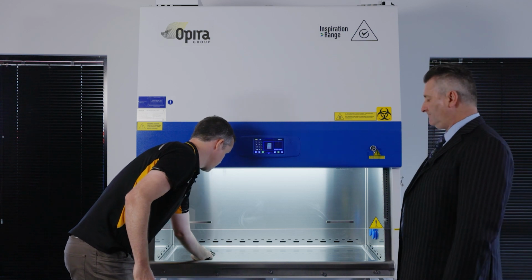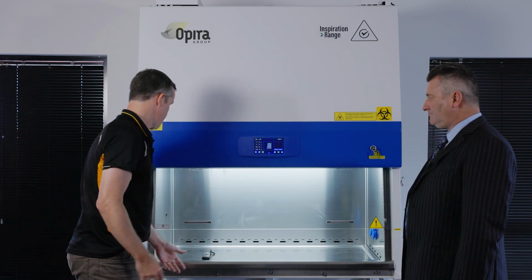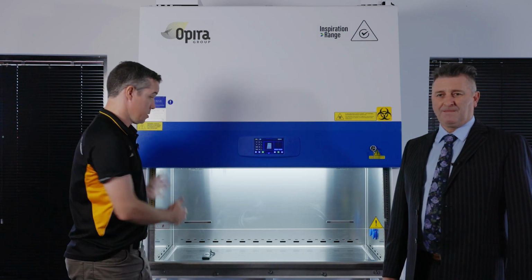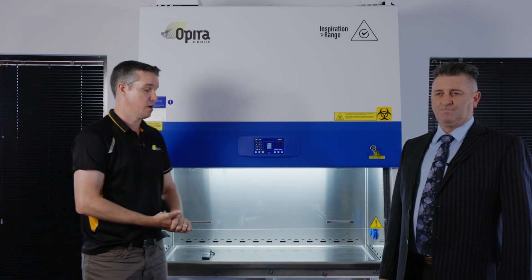So this is achieving well above the 430 minimum, and it's getting 730, so that's also above the average, and that's on the sides, which usually has the lowest lux readings. Okay, now we've finished the illuminance test.